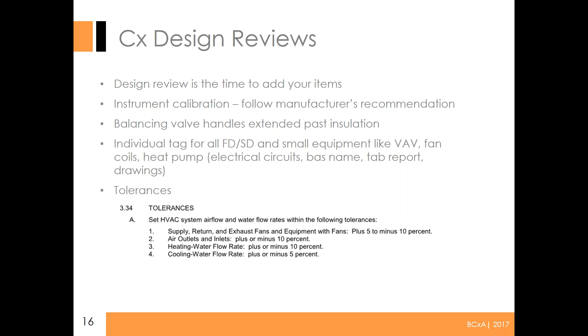Tolerances - that's a pretty big topic for TAB guys. Here's a typical example where they'll say +5 to -10%, air outlets plus or minus 10%, heating plus or minus 10%, chilled water 5%. This is reasonable in my opinion, but NEBB will recommend plus or minus 10% for everything. So +10, -10, and the client pays more for closer tolerances. That's something they should know. Often the limitation of instruments will make it harder to get any tighter than 10% on some devices.